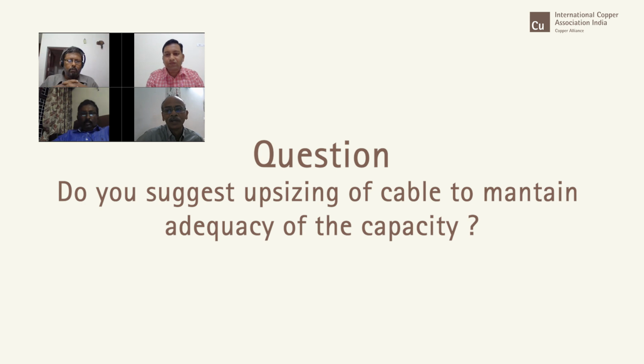Suppose for that particular circuit it is mandated to be 1.25 times the maximum current. But if you find that there is a cable which has just about 1.1 times ampacity, then it is better to go for a cable which will be 1.6. Suppose it is only 2 amperes more, I would suggest that you go for it, because that would be much safer than undercutting, saying okay, chalta hai. So that is where the whole problem comes.